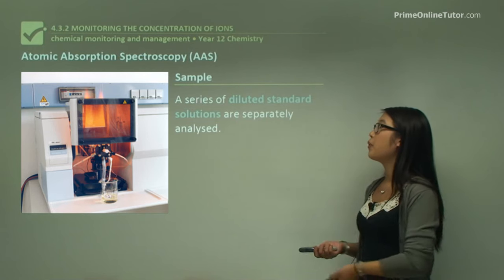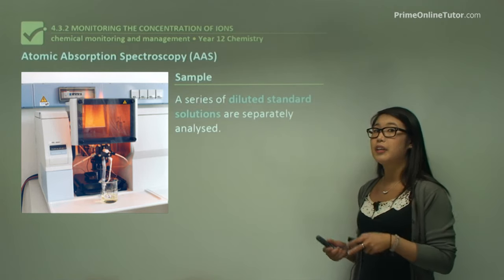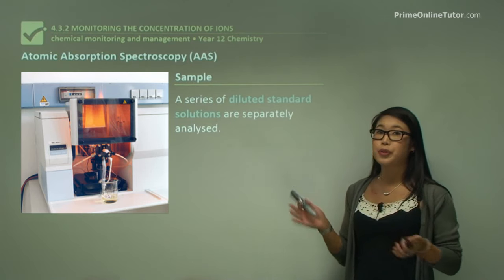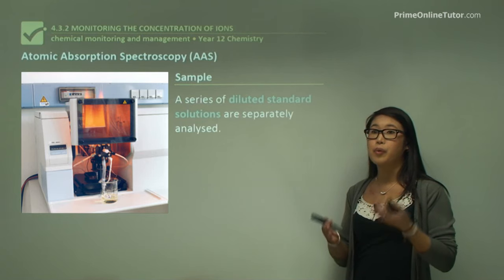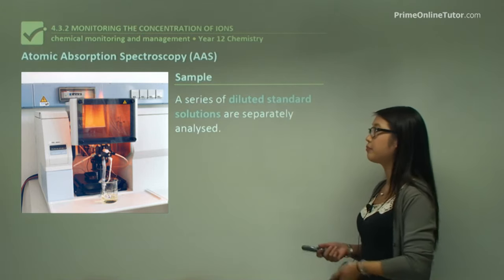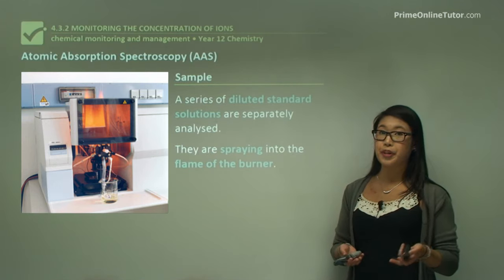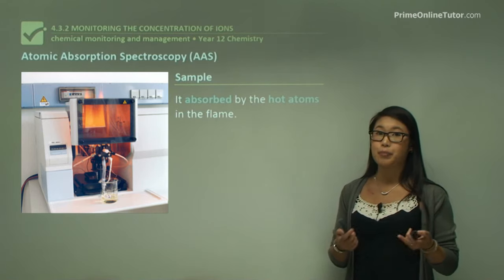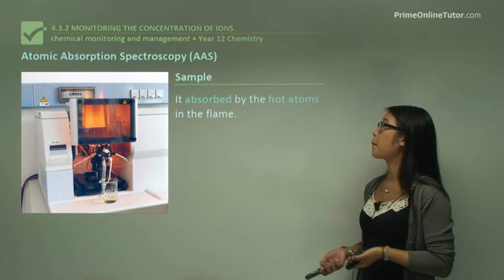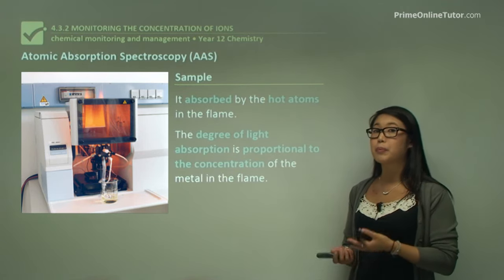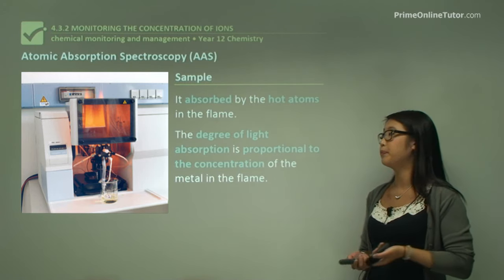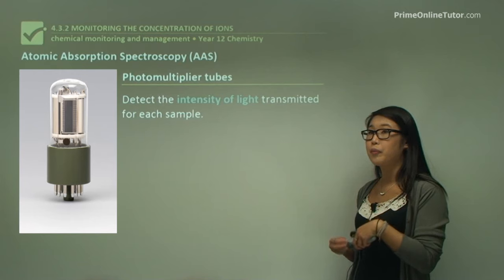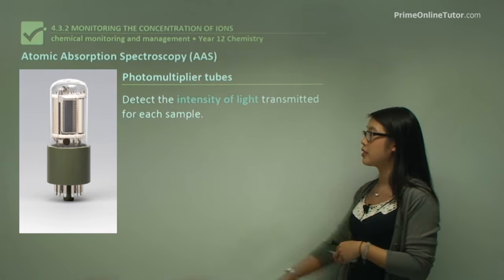When testing a sample, we first have to make up a series of diluted standard solutions of known concentrations, which we analyze separately in the AAS machine. First, we spray the sample into the burner, then light from the hollow cathode lamp is passed through it, and the sample absorbs the light at the specific frequencies. The degree of light absorbed is proportional to the concentration of the metal ions in the sample. The photomultiplier tube is used to detect the amount of absorption.